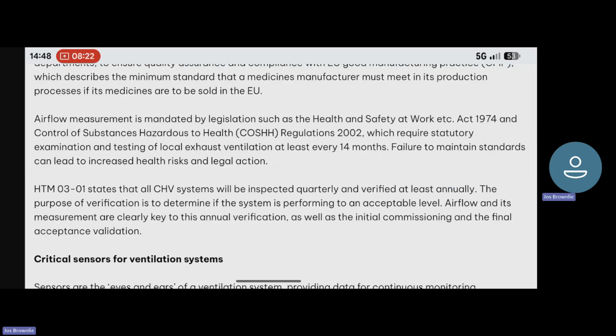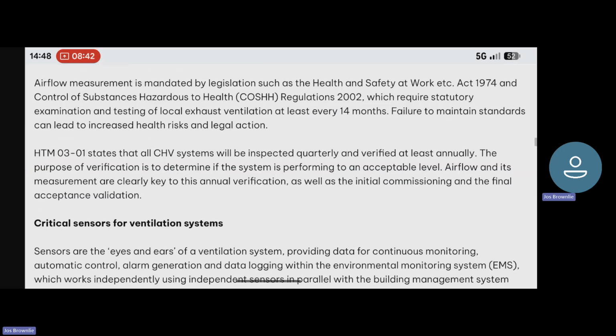Airflow measurement is mandated by legislation such as the Health and Safety at Work Act 1974 and the Control of Substances Hazardous to Health Regulations 2002, or COSHH, which requires statutory examination and testing of local exhaust ventilation at least every 14 months. Failure to maintain standards can lead to increased health risks and legal action.